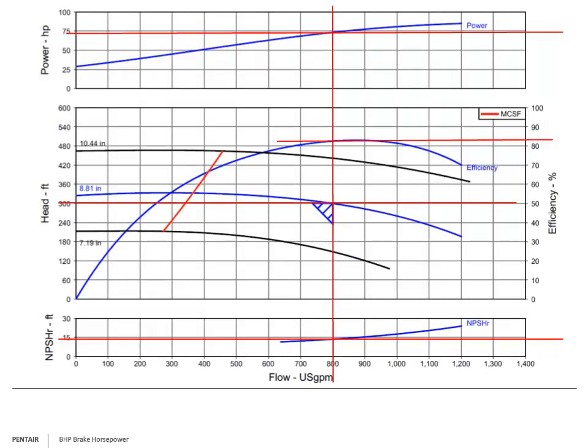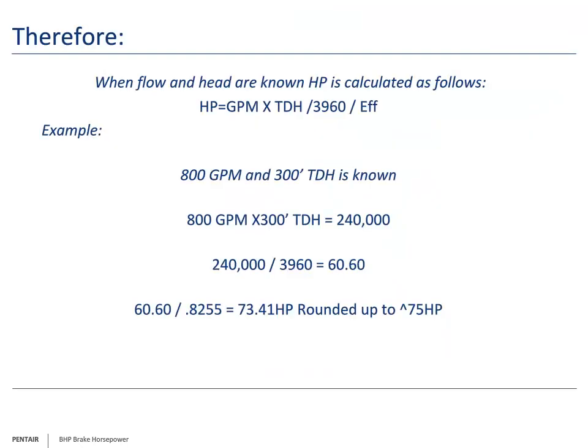Doing the math, we calculate that the system will need 74.81 horsepower, rounded up to 75 horsepower. Now let's prove the results. Going to the sizing program and inputting the gallons per minute and total dynamic head, we see we are in fact pretty spot on. Digging into the output a little deeper, we find the efficiency is in fact 82.55%. Going back to the formula now using 82.55%, we see the horsepower needed is 73.41 horsepower, which still rounds up to a 75 horsepower motor.